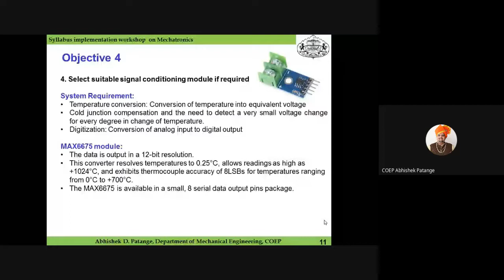So I was talking about the signal conditioning module. To perform three functions, converting temperature into equivalent voltage, cold junction compensation, and digitization, we have this MAX 6675 module, which costs only 100 or 150 rupees. It has been selected because it has 12-bit resolution. It resolves temperature to 0.25 degrees Celsius, and it allows readings as high as plus 1024 degrees Celsius, and it is available in a very small size, with 8 serial data output pins. That is why this signal conditioning module was selected.